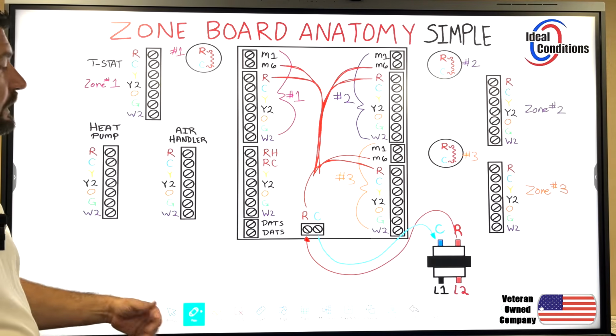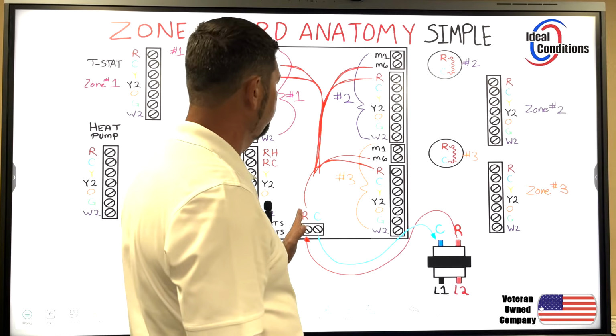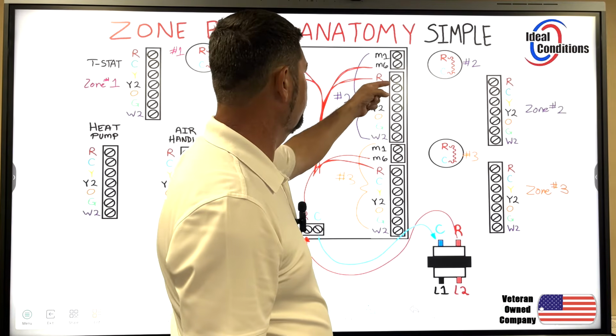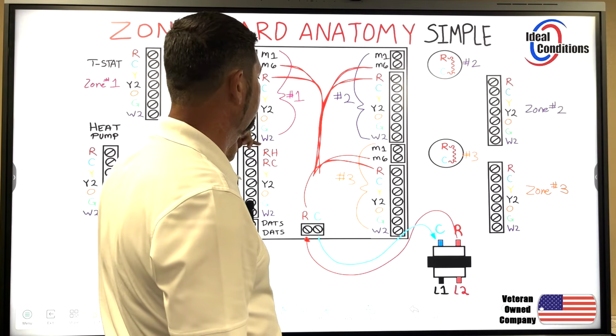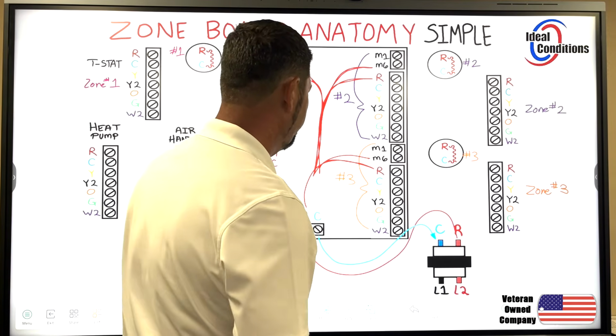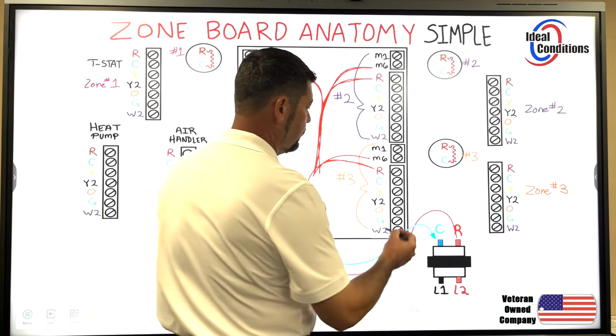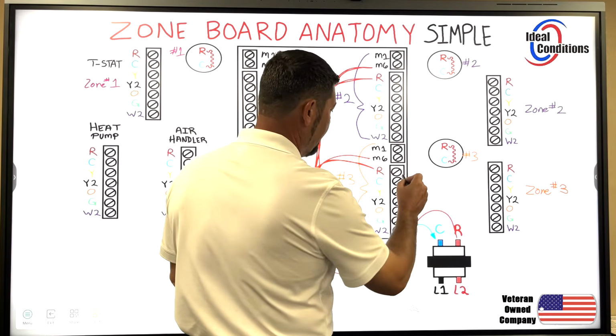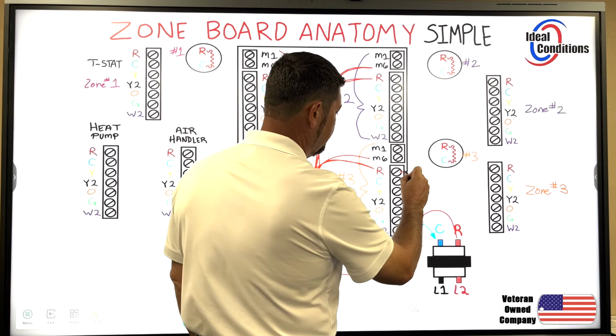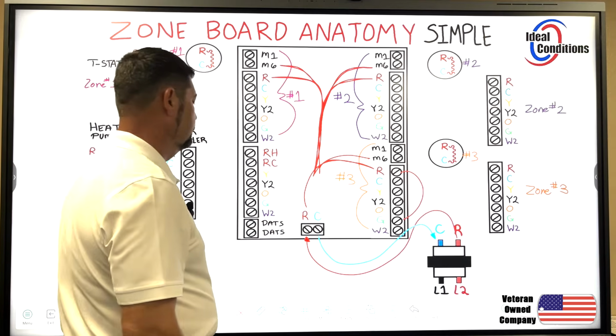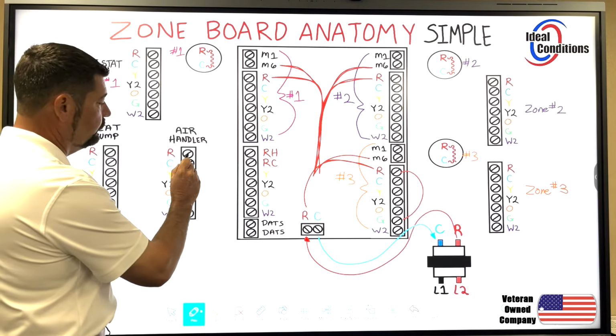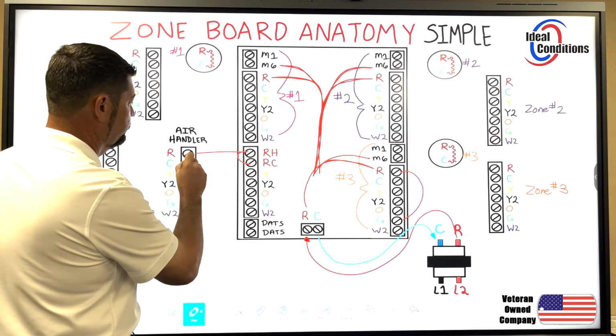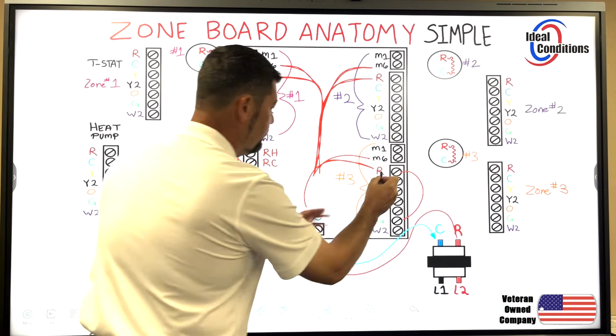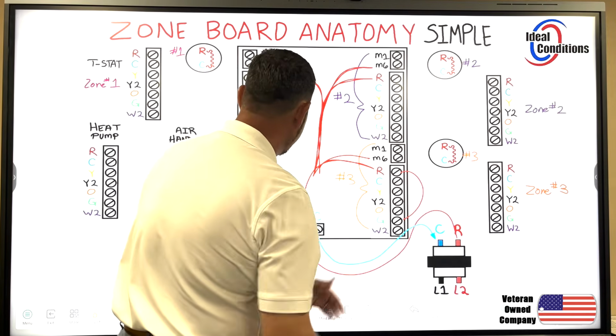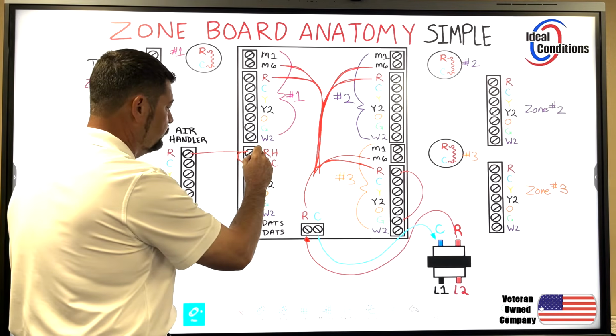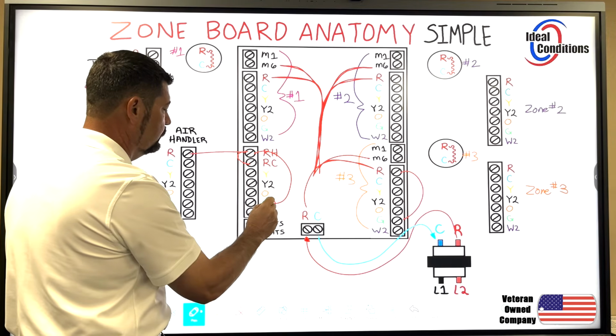And that's what it's going to take, is to put that 24 volts here, and then through the zone board, your zone board's landing 24 volt power supply on every one of these. You're never going to get a signal back on anything else. Never. But if I were to sit here and just take a wire and say, I want to just test my zone board out, I can take red and energize any one of these, and as long as I have 24 volts primary here, then the moment I take 24 volts here and energize it on, say, G, for example, then I should see 24 volts appear through the zone board right here.